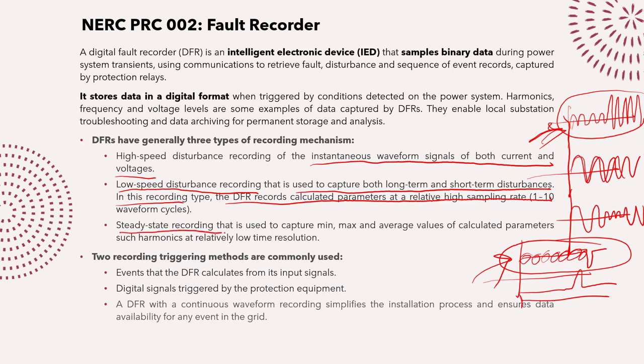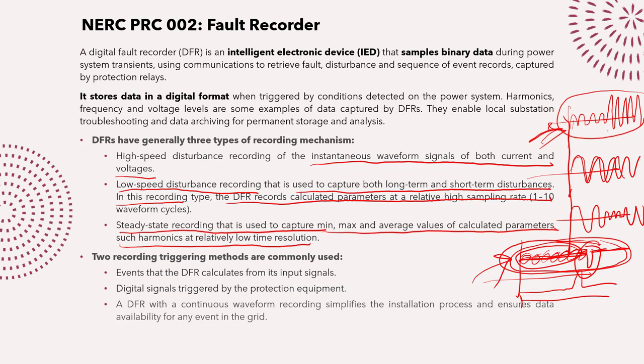The third type is steady-state recording, which captures minimum, maximum, and average values of calculated parameters such as harmonics at relatively low time durations. This can be used for long-term and short-term analysis — capturing fault conditions as well as pre-fault system operating conditions. For example, it can record harmonic content such as the second harmonic during transformer charging, and track maximum or minimum voltage over a given period.